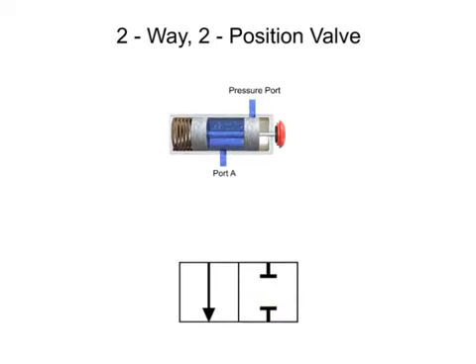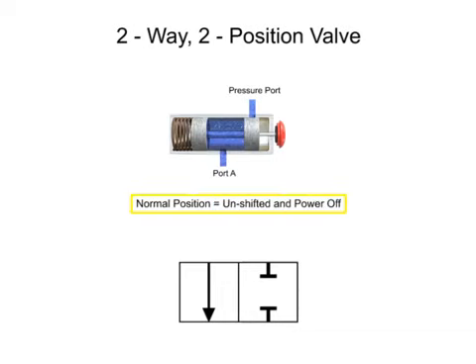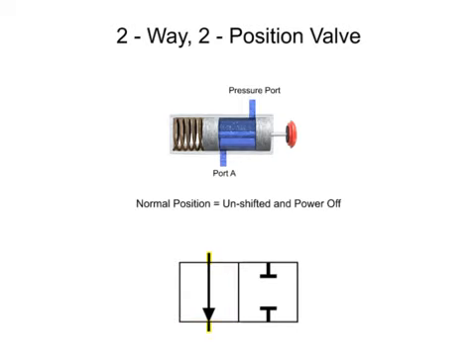Lines are drawn to indicate the normal position of the valve. The normal position is defined as the position of the valve when its spool is unshifted and the power is off. This means that any mechanical actuators, such as springs, are in their non-actuated positions, and electrical actuators, such as solenoids, are powered off. The normal position can also be referred to as the unshifted, de-energized, or unactuated position. In this case, position one is the normal position, so the lines indicating the normal position are drawn in the first box.